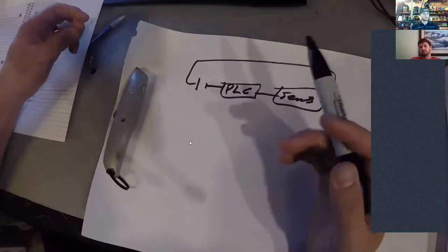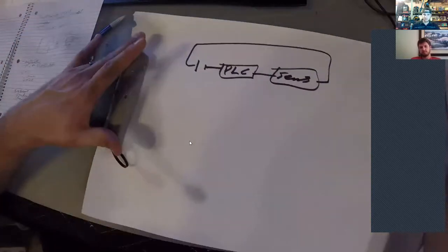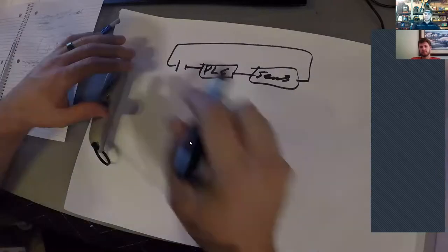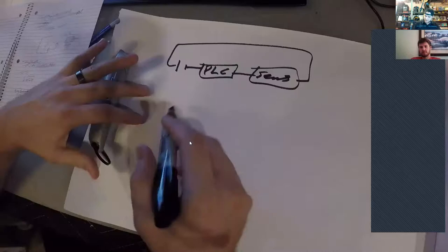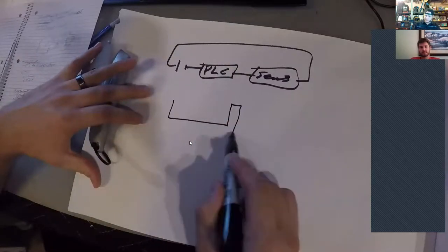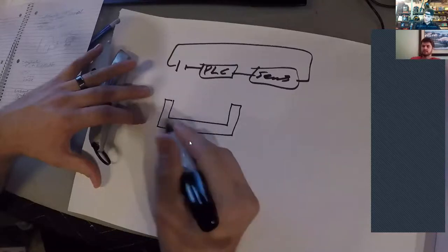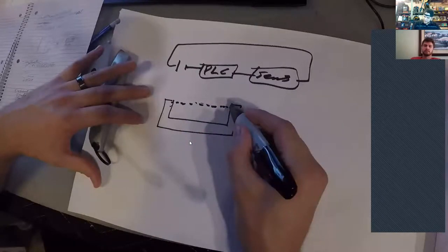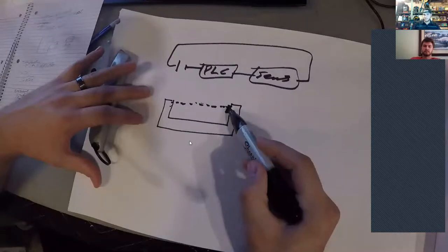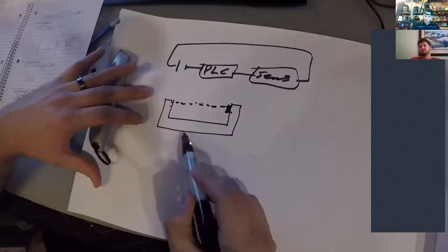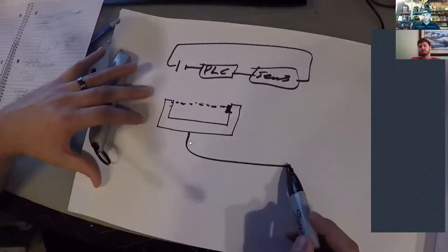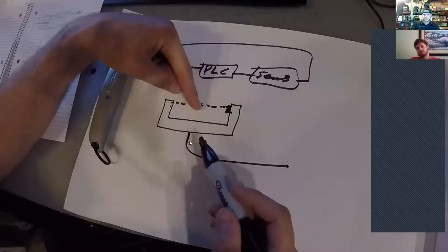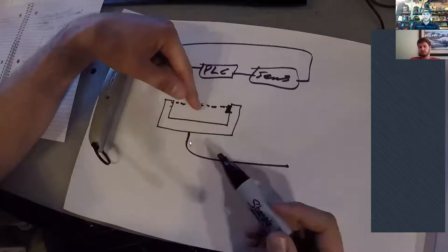So I just wanted to give you a heads up when you see vendor schematics of PNP or NPN, they're going to look like this, because our sensor has three wires. So when you wire the sensor up, you bring the positive brown wire to the positive terminal of your power supply, the negative blue wire to the negative terminal, and then you bring the black wire from your sensor to your input on your PLC.